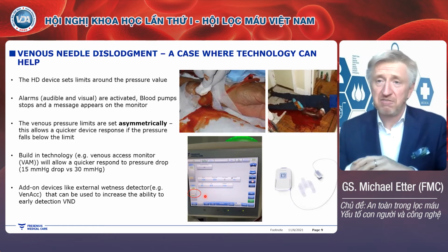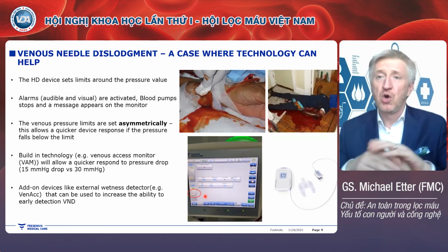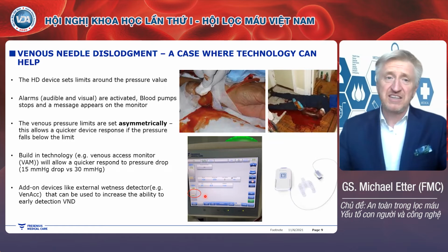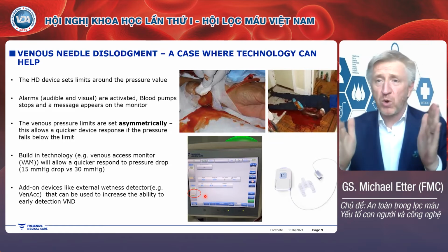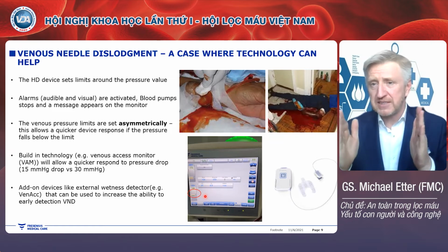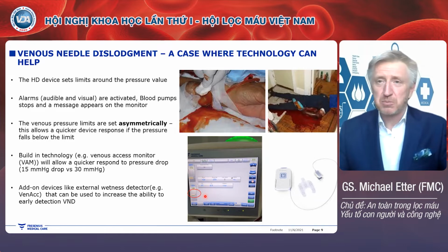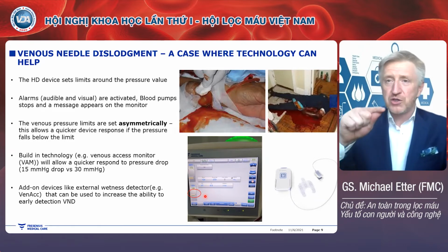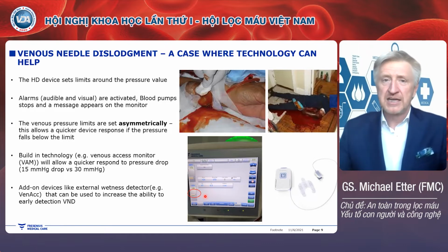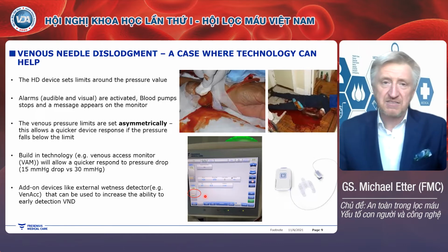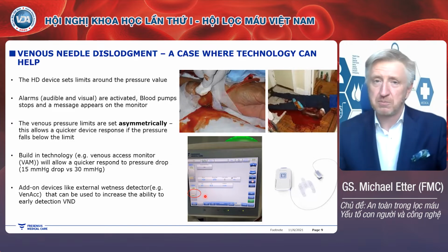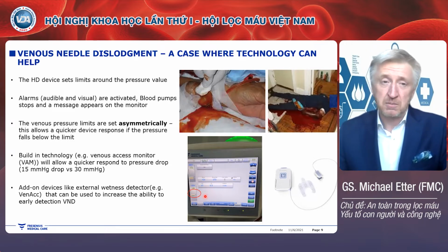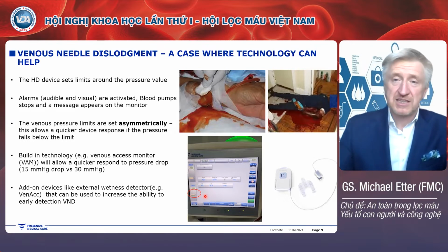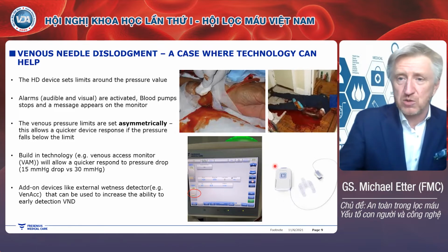Newer devices have built-in technology which, on top of these standard venous pressure alarms, which work in a rather wide pressure window, can actually detect pressure drops earlier, not just by absolute measurements, but by contour analysis of the pressure curve. For example, one device is the venous access monitor that can detect pressure drops as low as 15 millimeters mercury. And then you also have some external add-on devices, as you see here.